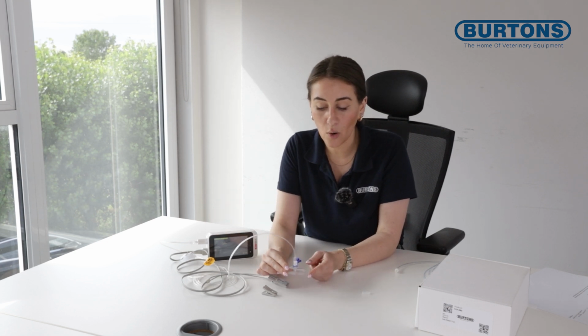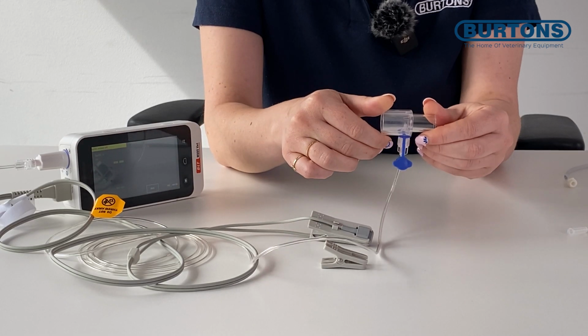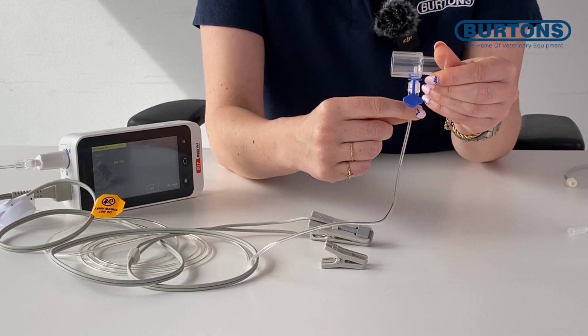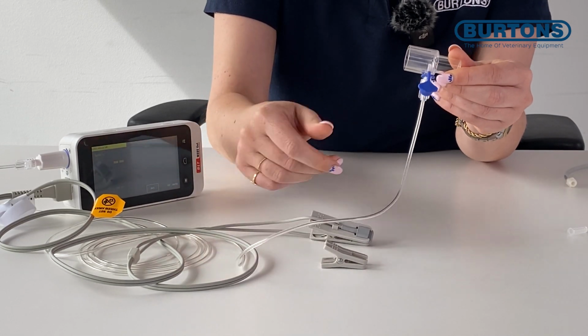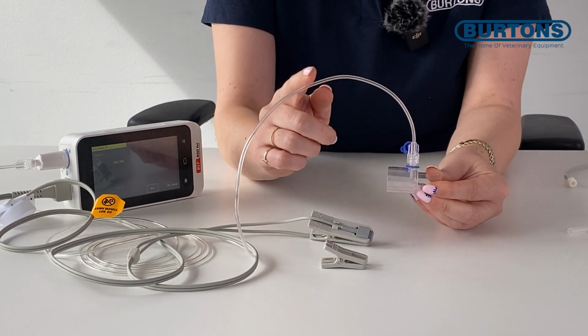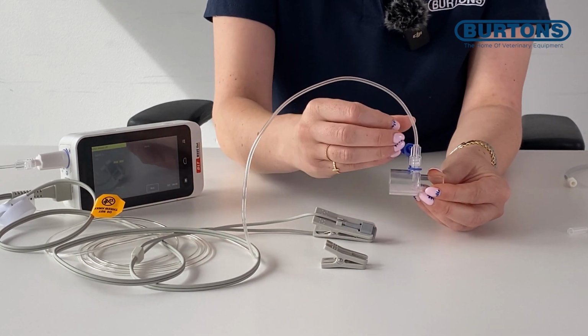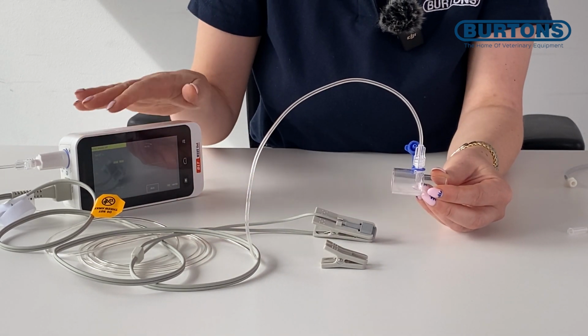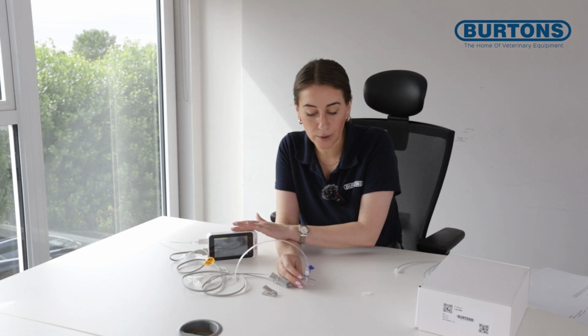So as a result, I always want my sample line to be attached uppermost rather than attached down at the bottom, because water vapor will obviously flow with gravity. You still will get a degree of water being absorbed by the machine because of the suction pump built in, but we just want to try and deter as much water as possible from getting to the machine and causing damage to the internal module.